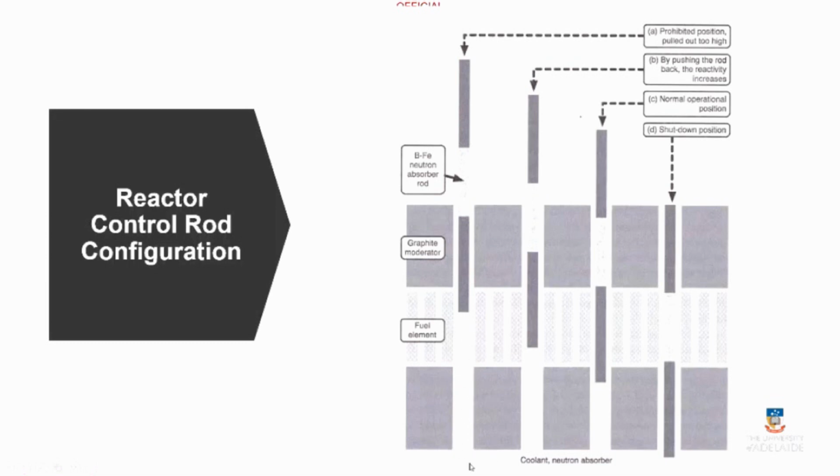That water acts as an absorber, which means your reactor also starts to slow down, which is great. But the problem is that if you're too far out, as you push this in, this is what is referred to as the tip effect. That tip pushes out the water and it creates a power surge, because this is where the rods were normally expected to be kept when you're wanting to lift the rods up to a certain level.